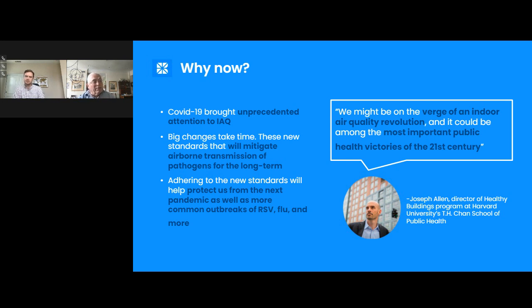With COVID, we're now belatedly asking: we want to increase ventilation, but how much? That's where ASHRAE and CDC have come in with recommendations. CDC's recommendation, I'd say, is a practical, achievable amount of ventilation based not on occupancy but on room volume, assuming a certain typical occupancy.